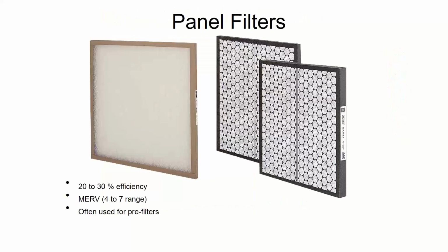A lot of systems get one of these cheap low-end filters that either don't have a MERV rating or they have really poor MERV ratings. If your filter looks like one of these filters, your filter doesn't do anything as far as germs are concerned. Your filter's there for the reason that we started putting filters in equipment to begin with. If you didn't know, the reason that HVAC has filters is not to make your air quality better. We don't care about you and your air quality. I mean, we do, right? But that's not why the filter's there. The filter's there to keep dirt off of the heat exchanger, to keep dirt off the evaporator coil, because if those things get dirty, they don't transfer heat very well, and then you don't get warm and cold like you want to. So that's why I put the filter there.